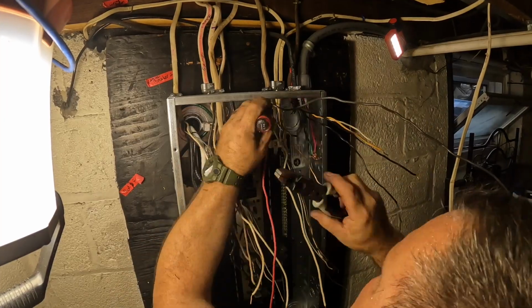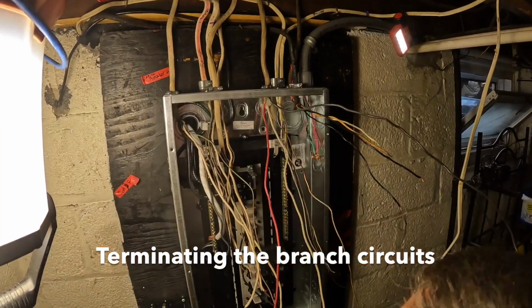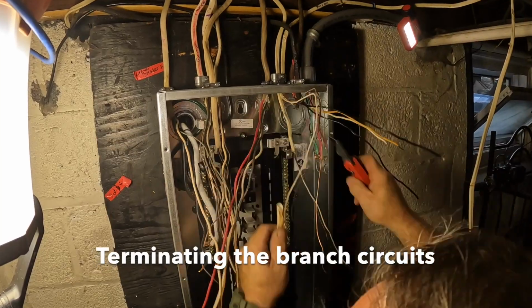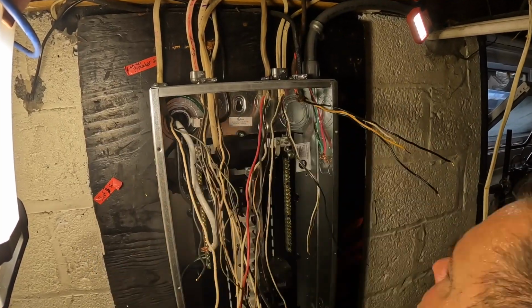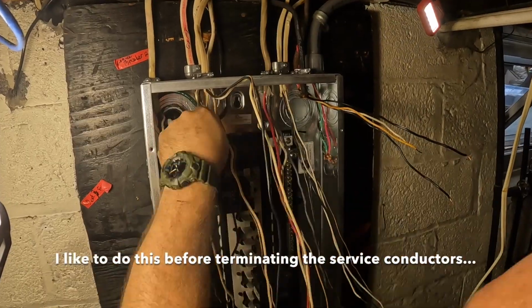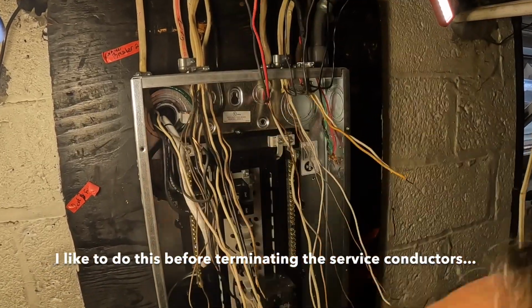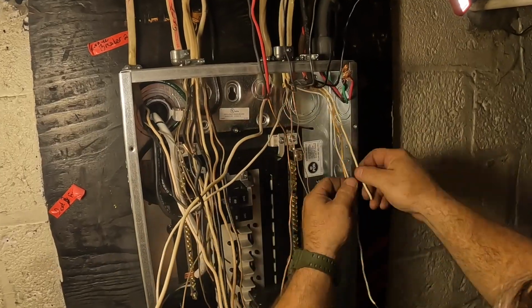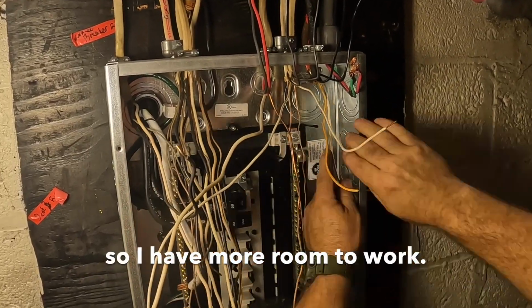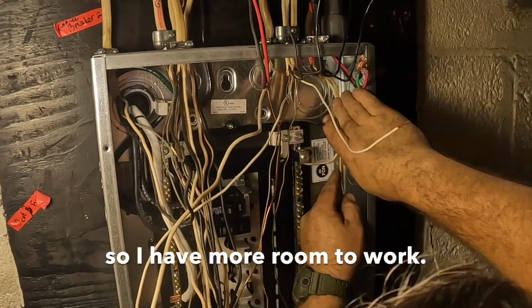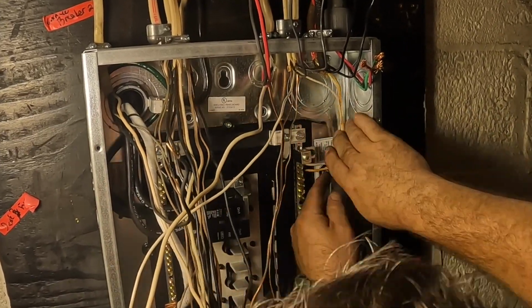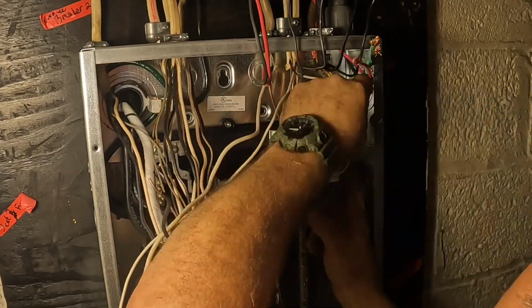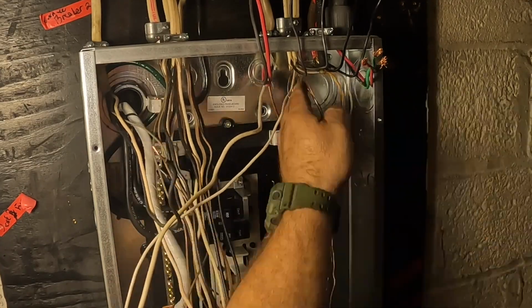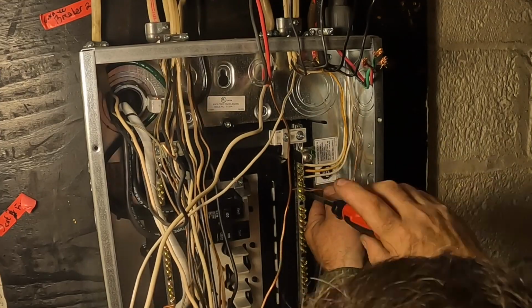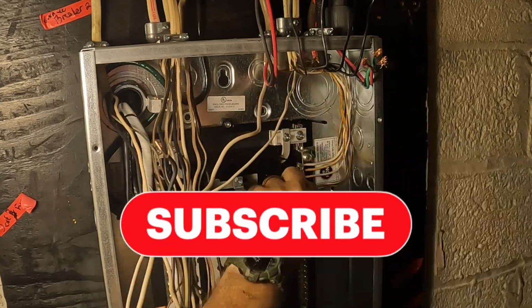So I guess you could say the nice thing about this particular panel upgrade is I'm using all non-metallic sheath cable, which is a bit easier to work with than an old armored cable. The other nice thing is I would say the majority of these conductors were long enough to work with without doing splices. And of course, I get this comment occasionally, but splices and wire nuts and that sort of thing inside an electrical panel is totally permissible. If you look at Article 312.8, you'll see all the information you need to know there about making splices inside of a panel. So if you think for a second that that's not allowed, you're wrong.